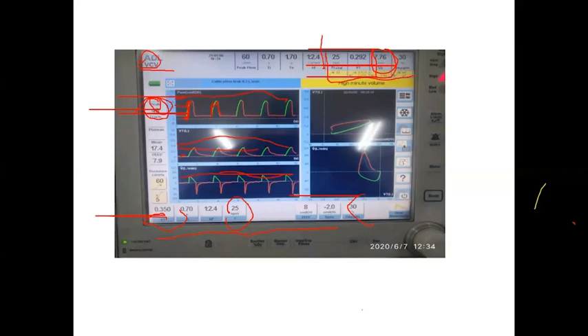Yeah, then, so this is what pressure I said, and this is tidal volume. You can see 0 level, x-axis and y-axis 0.5 for 500 ml. Tidal volume is 350, we fixed. You can see the constant tidal volume here, delivering inspiration, expiration. Yes, and you see the flow. Flow usually, what is the flow? How much of flow? You see when you inflate the balloon, the flow should go maximum inside. Then only the balloon volume will increase, right? So if the flow you are giving, any obstructions or anything is there in between, the flow will not reach the lungs properly, right? So there will be any changes here. This is the decelerating flow. I will discuss separately one by one.